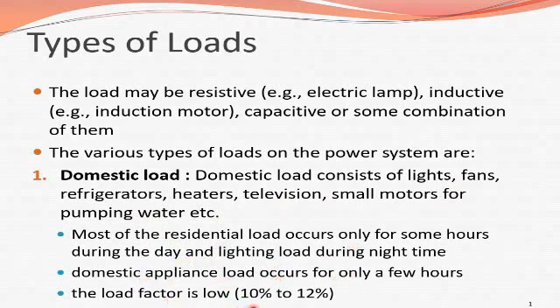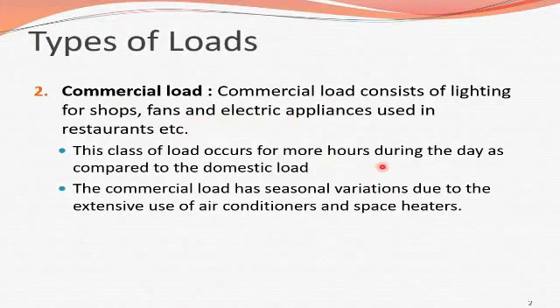The load factor for domestic load is low — 10% to 12%. The next one is commercial load. Commercial load consists of lighting, fans, and electric appliances used in restaurants and shops. This class of load occurs for more hours during the day compared to domestic load. Commercial load also has seasonal variation due to the extensive use of air conditioning and space heaters.